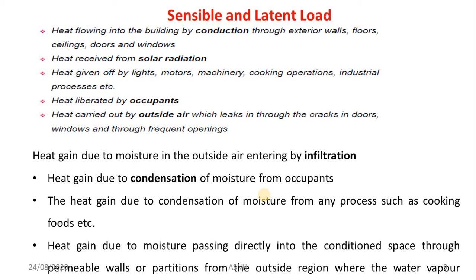While in case of the latent heat, the heat gain due to condensation of the moisture from the occupant. That is, take the example of human sweating, through which that latent heat load occurs. So we must have to consider such kind of factor. The second one is the heat gain due to condensation of the moisture from any process such as cooking and food. So here the phase change takes place. So in applications like cooking food, we must have to consider the latent load conditions. Similar way, the heat gain due to the moisture passing directly into the conditioned space through permeable walls and partitions from the outdoor region where the water vapors are more. Such kind of latent load we must have to consider while designing the capacity of the refrigeration and air conditioning system with the help of that sensible and latent heat factor.